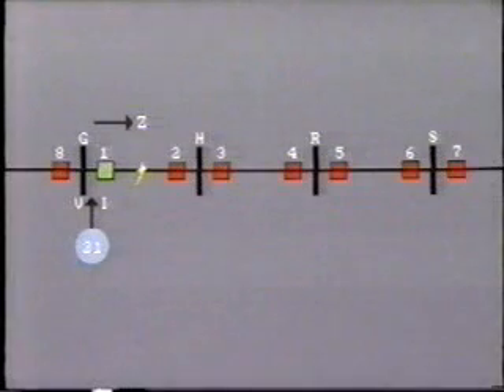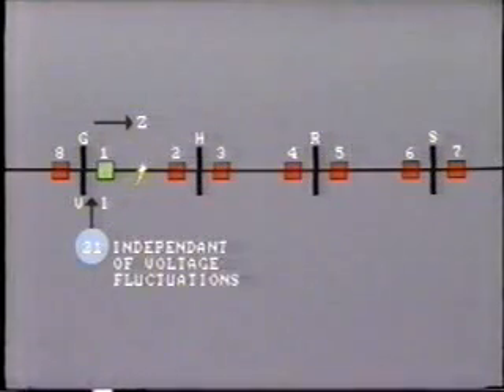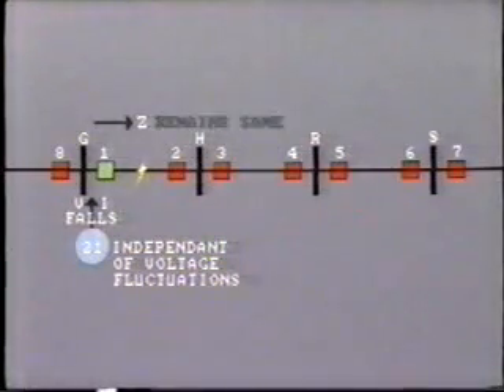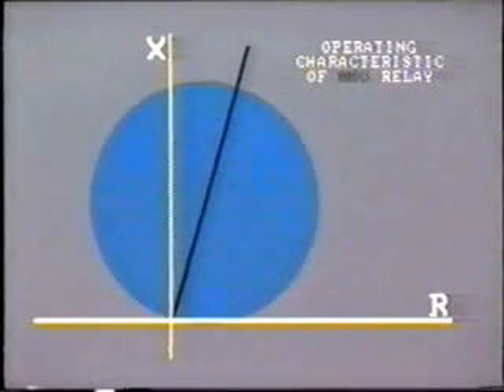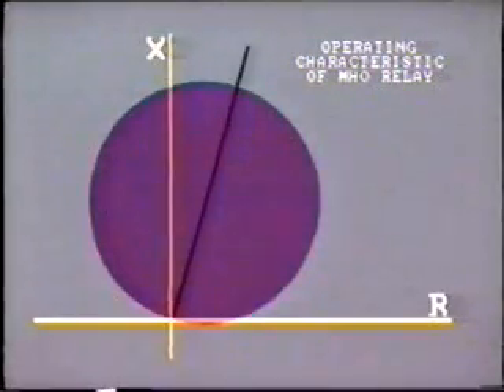An important characteristic of the distance relay is that it operates independent of voltage fluctuations. For example, if the voltage falls and the current falls correspondingly, the impedance measured remains the same. The operating characteristic of the relay is shown by the RX diagram here. This diagram is specifically for the Mho-type relay. The relay will operate once the impedance falls within this circle.